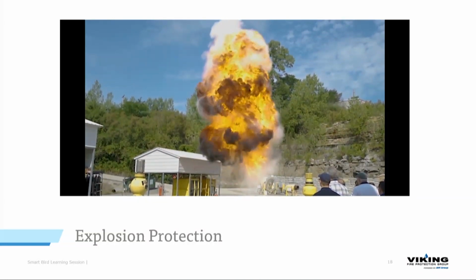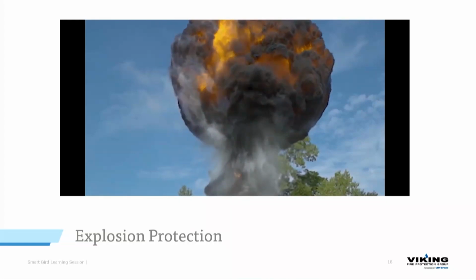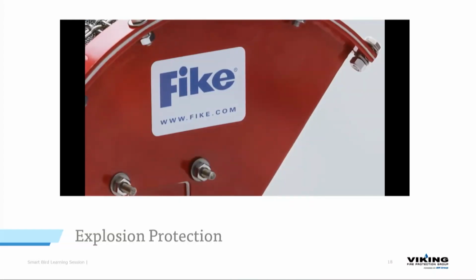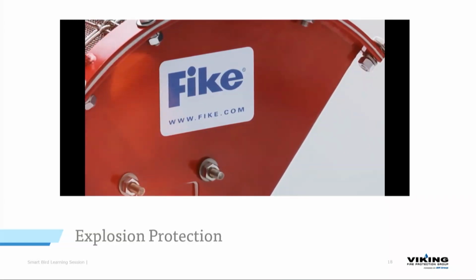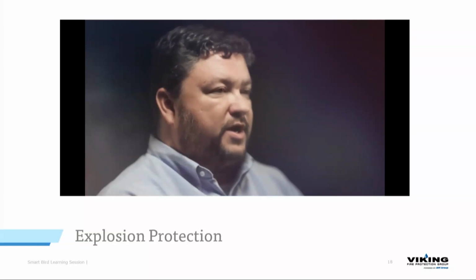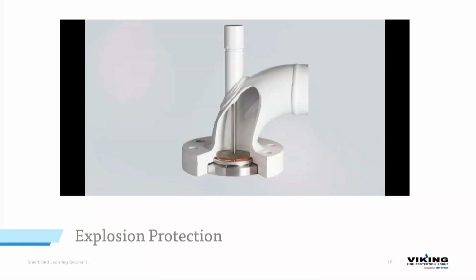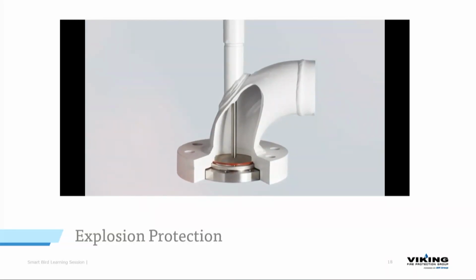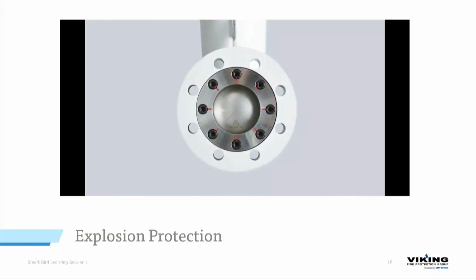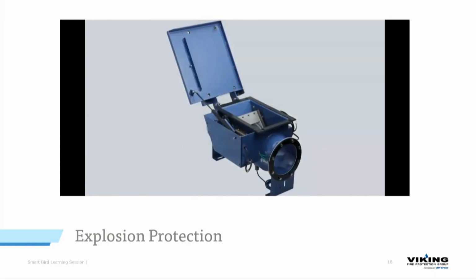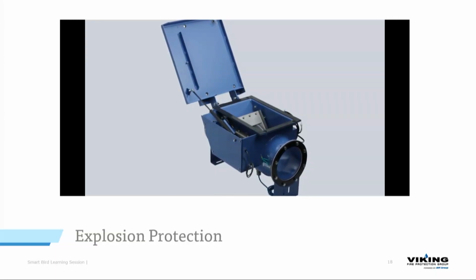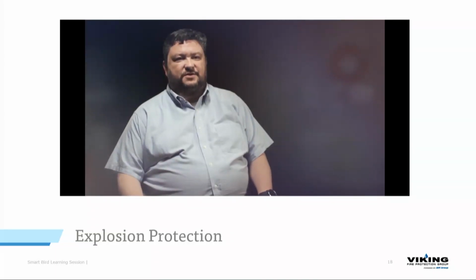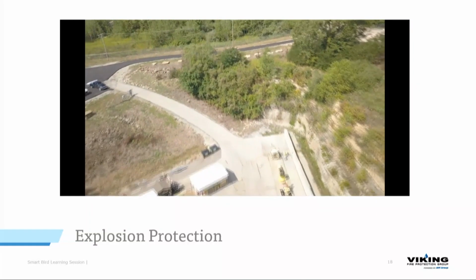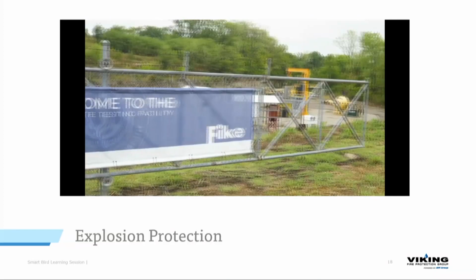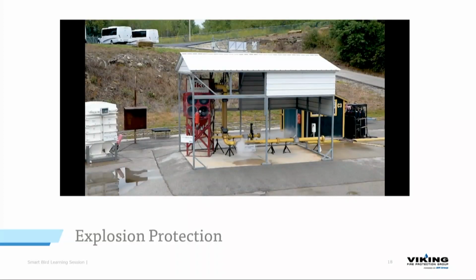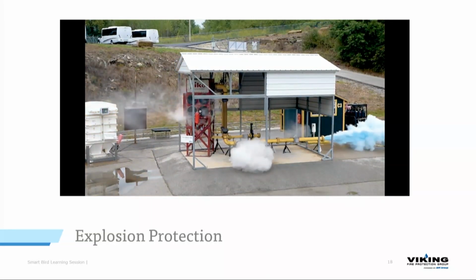We use a standard pressure detector to monitor the explosions, coupled with a very fast controller, and we're taking a reading off of that pressure detector 4,000 times per second. Within a millisecond, when we see a pressure rise, we can make a decision of whether or not that is an actual explosion and react to it by firing off one of our output devices, a suppressant container, or closing different isolation barriers. We have to be very fast and work within milliseconds to prevent the explosion from spreading or creating an overpressure condition. Fike continually improves our explosion protection solutions through new product development. We do a lot of testing in our remote testing facility to understand the science behind explosions, and we can then create the products that best control and protect people against those explosions.